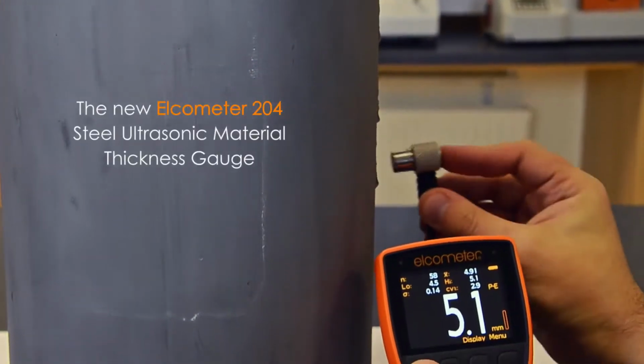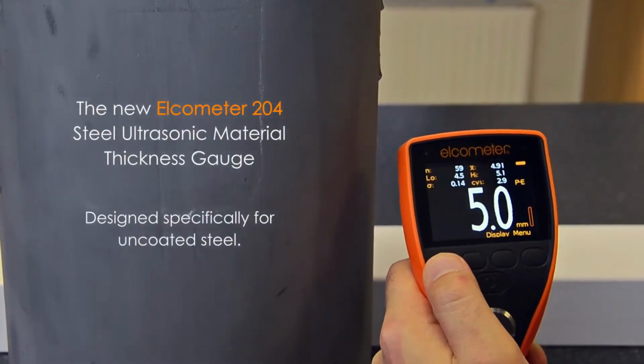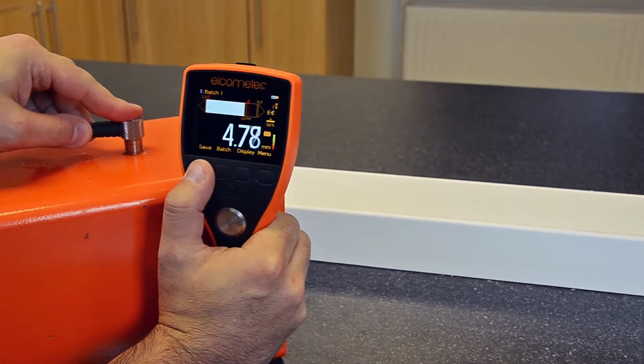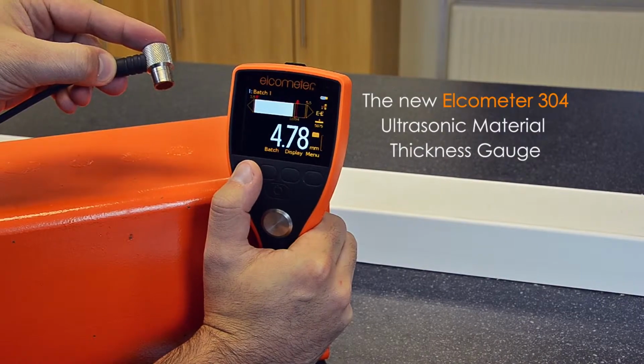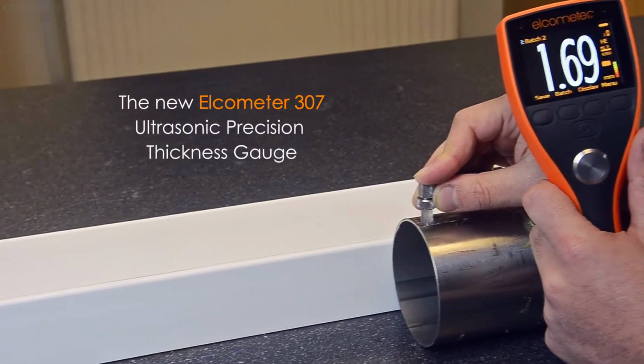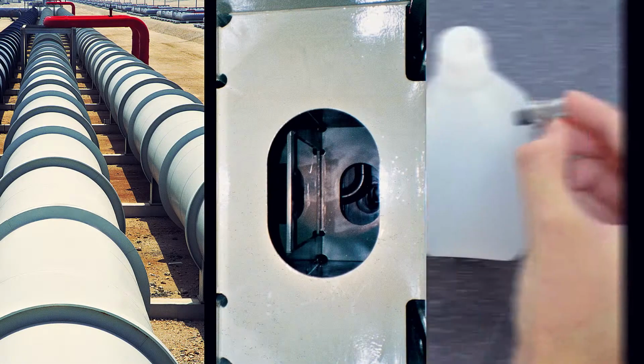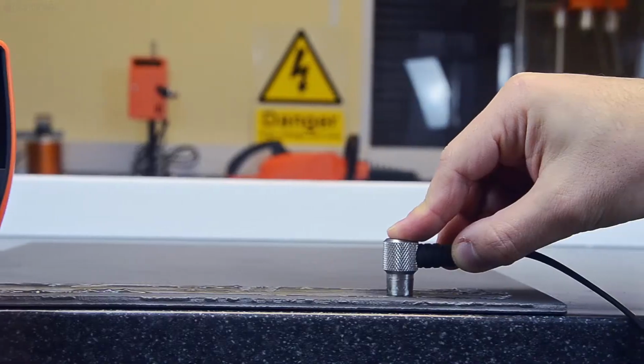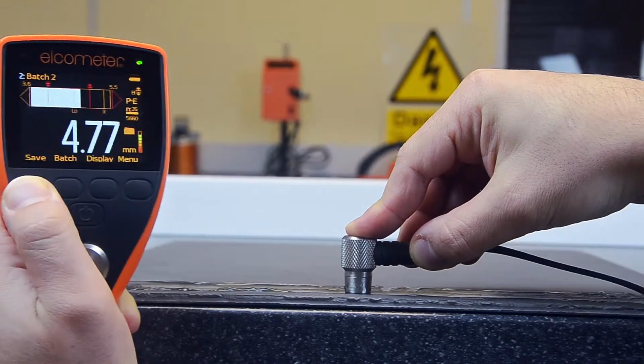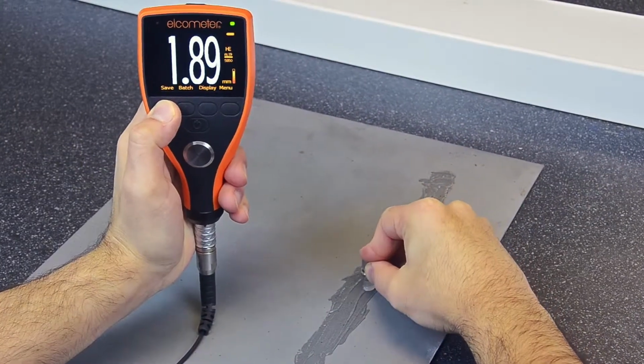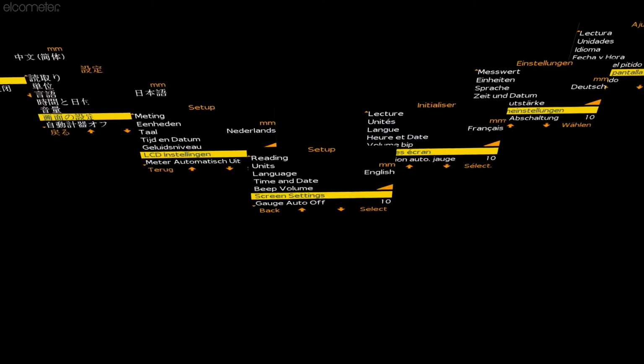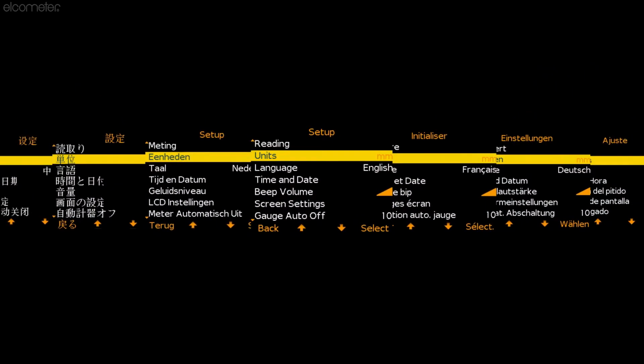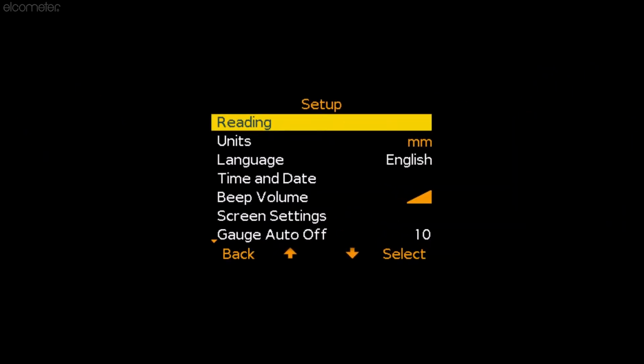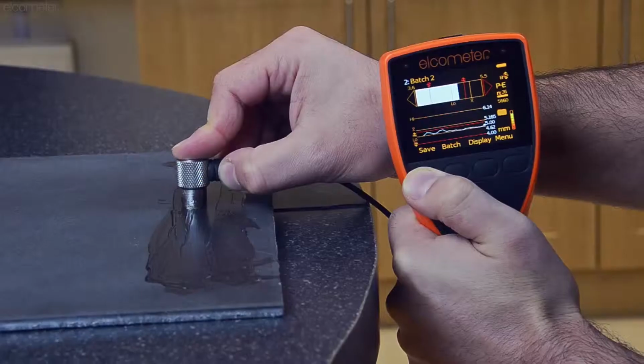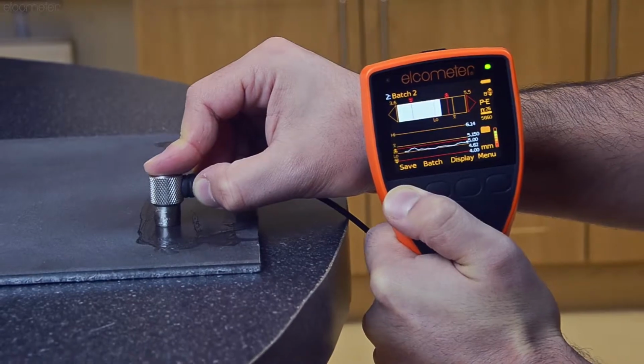Unlike the entry-level gauge, the Elcometer 204, which only measures the thickness of uncoated steel, the new Elcometer 304 and 307 are ideal for almost any coated or uncoated material, and have a wide range of applications, including pipelines, storage tanks, or thin plastic bottles for example, making this range of Elcometer ultrasonic thickness gauges versatile and reliable, providing highly accurate material thickness measurements. With its easy-to-use menu system in multiple languages, the Elcometer 304 and 307 thickness gauges can be used straight out of the box, with little or no training required.